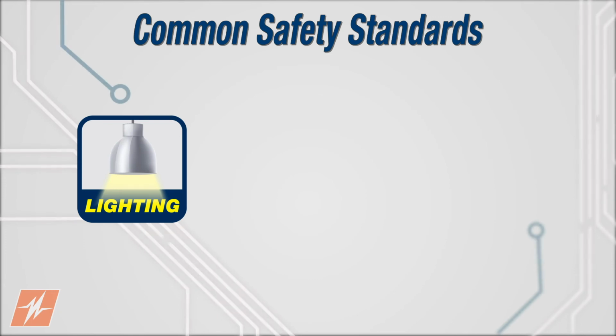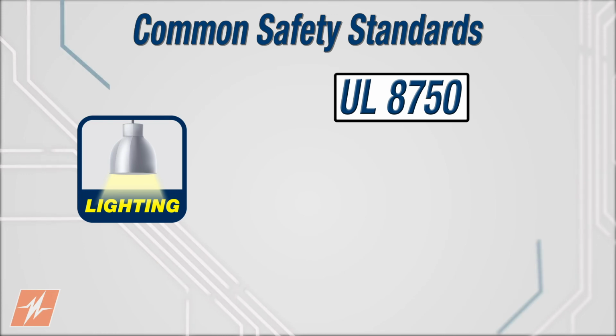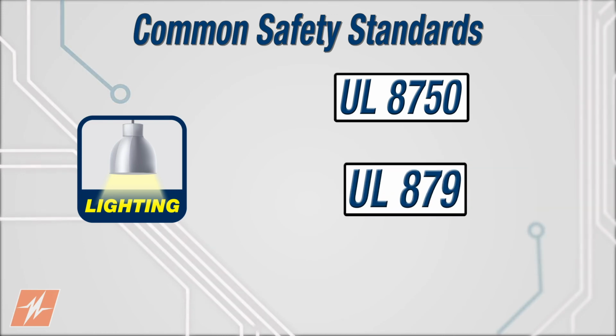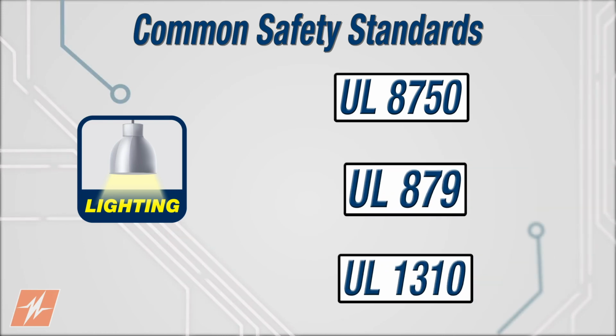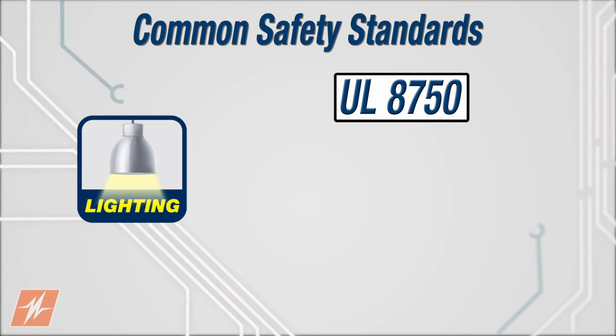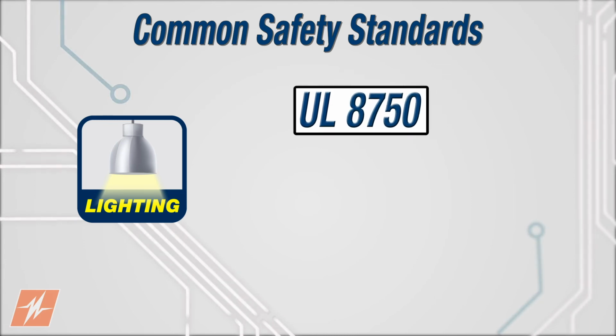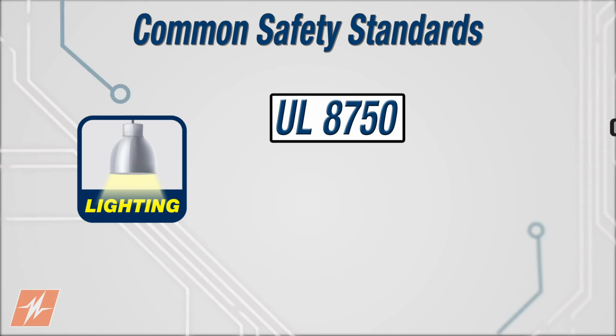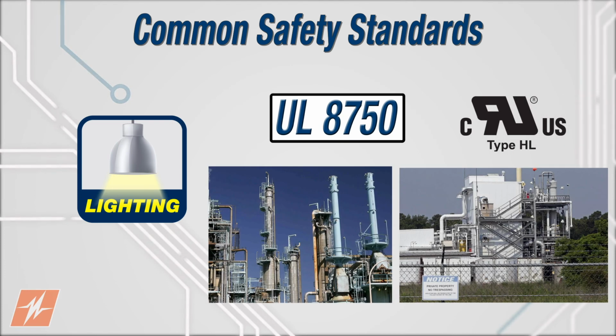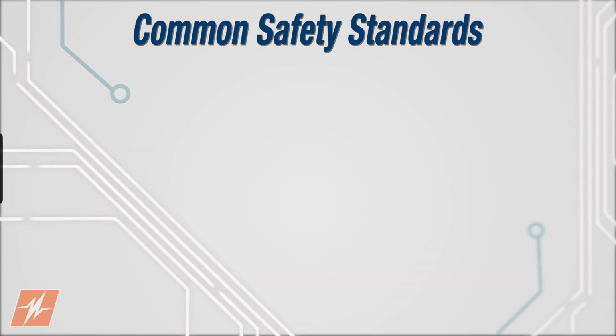Lastly, the common safety standards relating to the lighting industry are UL 8750, UL 879, and UL 1310. UL 8750 covers light-emitting diode equipment for use in lighting products. Products certified to this standard can also obtain Type HL designation. This designation indicates the product is intended to operate in hazardous locations such as oil refineries and chemical plants.